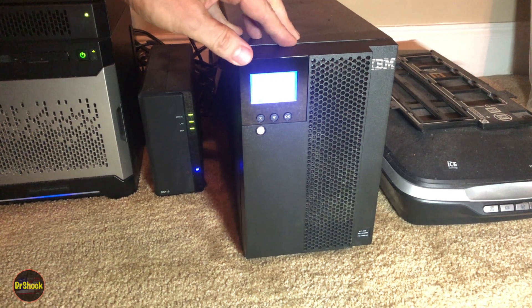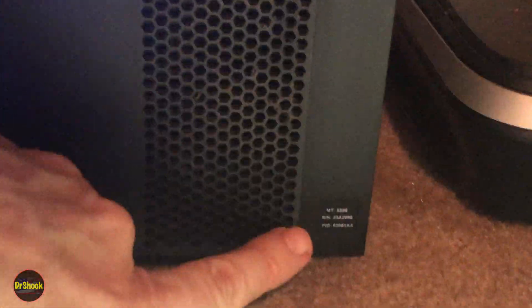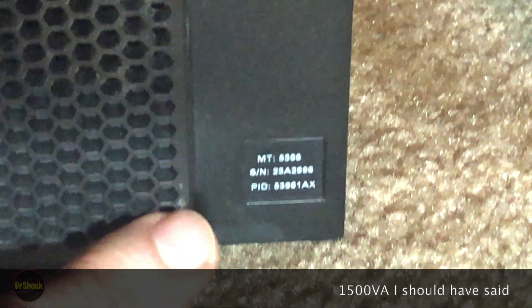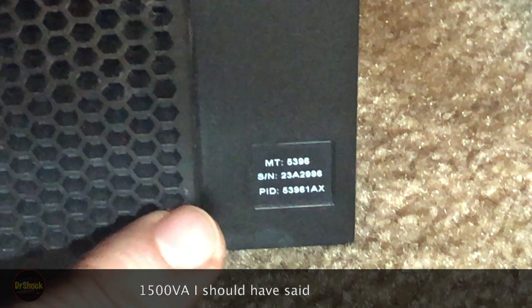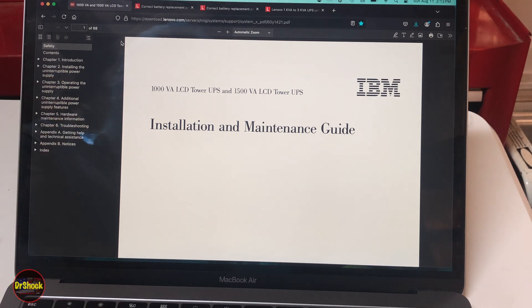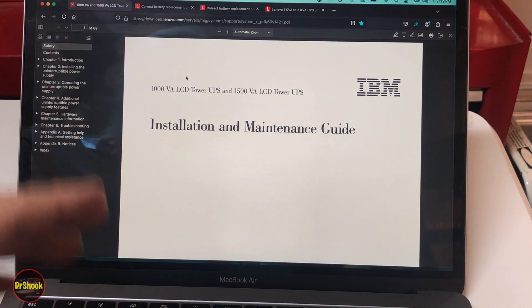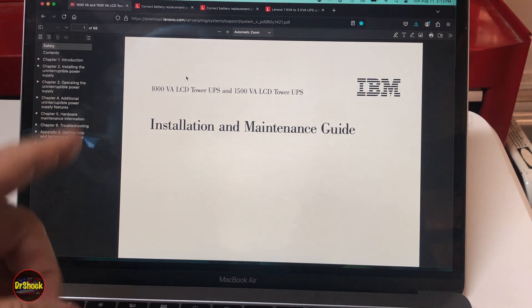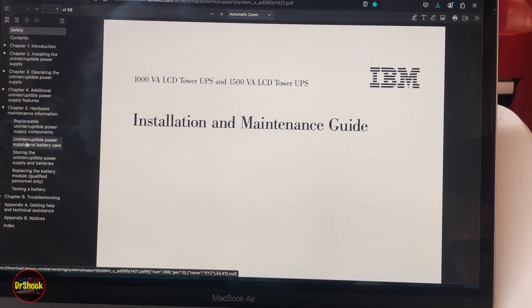Before we do anything, let's look at the service manual. This is a 5396 — there are several different flavors. This is the 1500 VA level; there's also a 1500 VA level. I think there are three different models — I'll put that in the description. So this manual is hosted on lenovo.com, but it's an IBM manual. IBM sold the business that included these UPS units to Lenovo at the beginning of 2014 — over 10 years ago. Let's go to the 'Replacing the Battery' section.